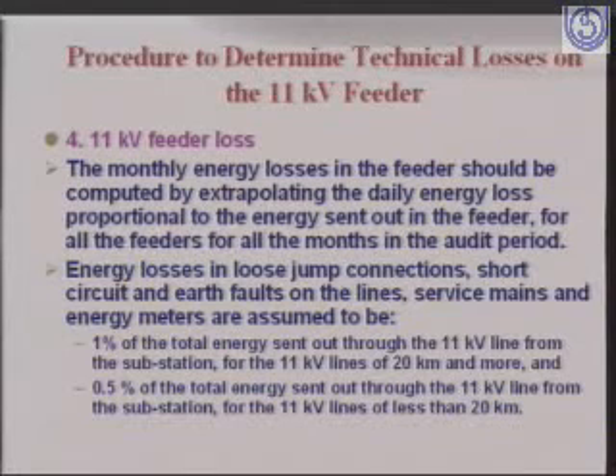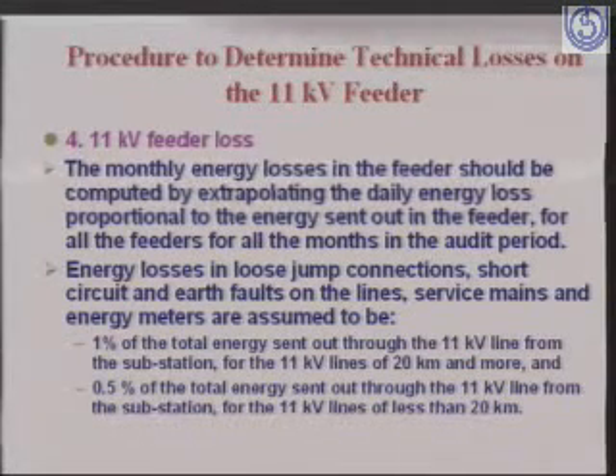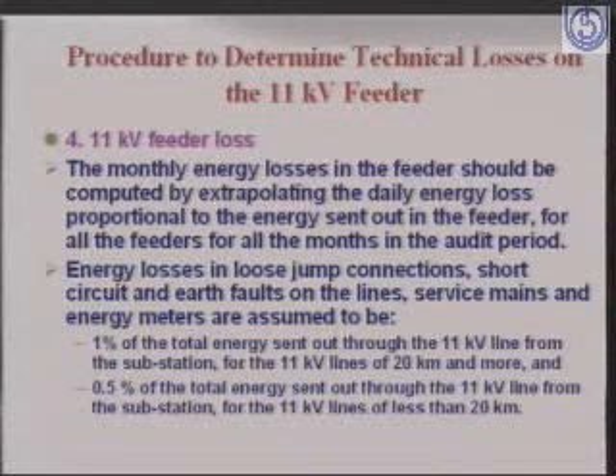Then energy losses in loose jump connections. These are losses which have to be estimated because they cannot be measured. So in your course book the loss factors have been given: 1% of the total energy sent out through the 11 kV line from the substation for 11 kV lines of 20 km and more, and 0.5% of the total energy sent out through the 11 kV line from the substation for 11 kV lines of less than 20 km. These are the losses for the jump connection, short circuit, earth faults, service mains and energy meters. These are to be assumed.